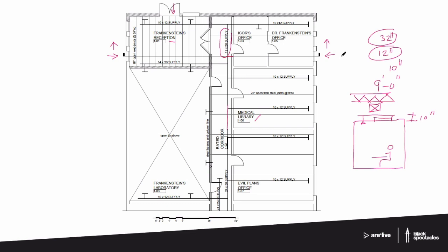You wouldn't want to have the floor change heights or the ceiling change heights or anything. So you have to just set the ceiling height and then set the floor height, which means you have to be able to accommodate the biggest duct that you're going to have. So get rid of that so we can put a new number in. Let's scan around and find. There's a 10, that's too small, that's just even smaller. Those are all 10s. I got another thing. Oh, how about right there? I got a 24 by 30 and a 24 by 24, which means this is 24 inches.